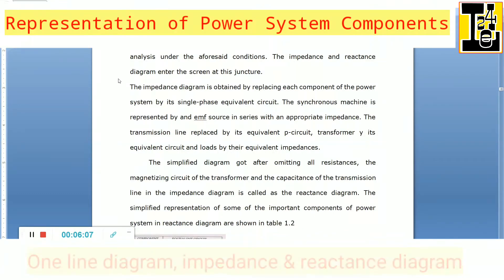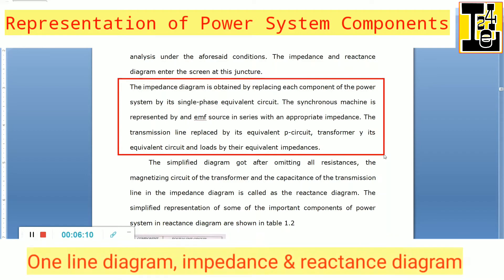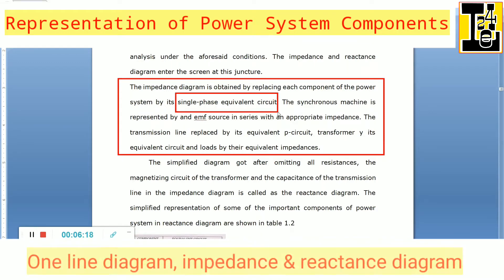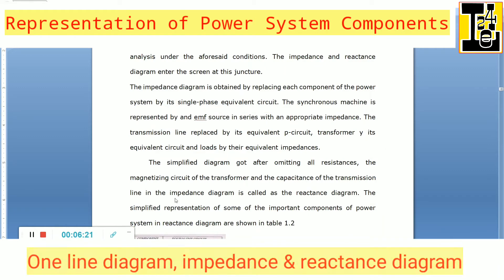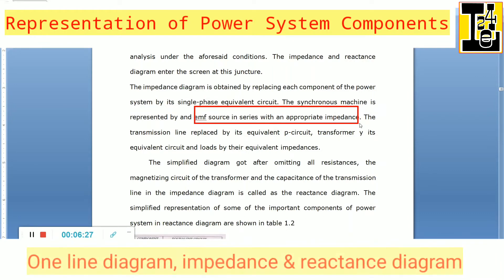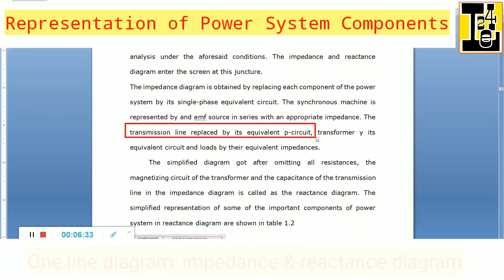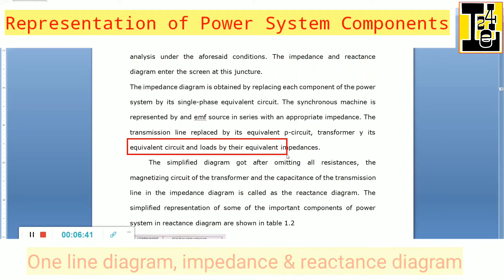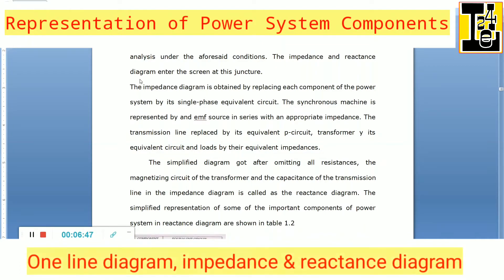The impedance diagram is obtained by replacing each component of the power system by its single phase equivalent circuit. The synchronous machine is represented by an EMF source in series with appropriate impedance. The transmission line and transformer are replaced by their equivalent circuits, and the loads are replaced by their equivalent impedances.